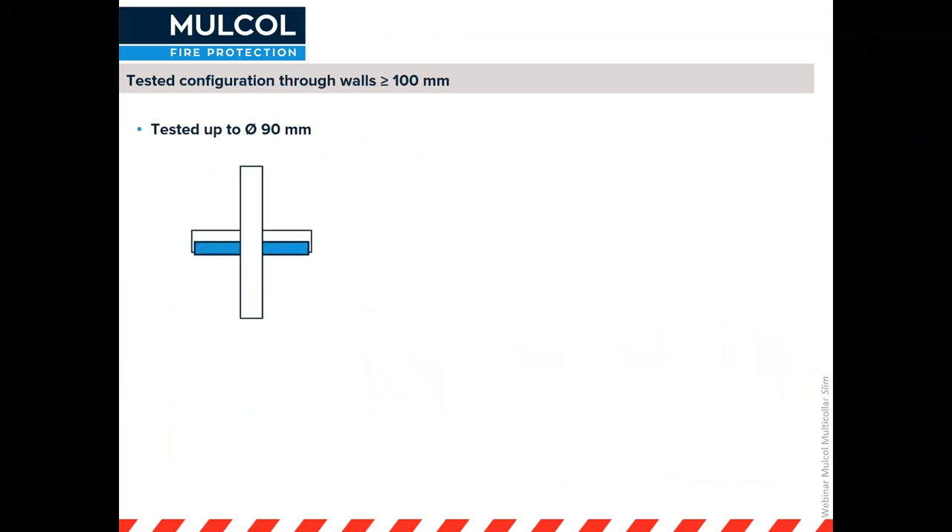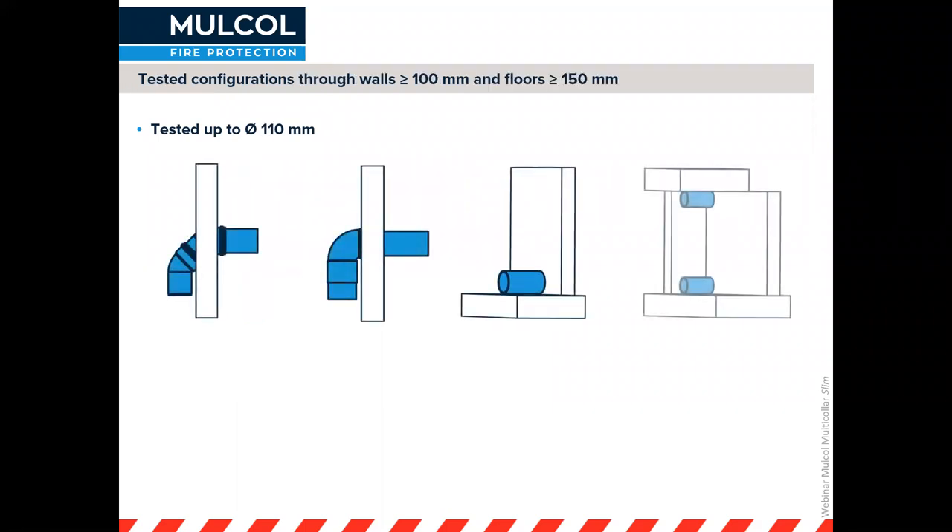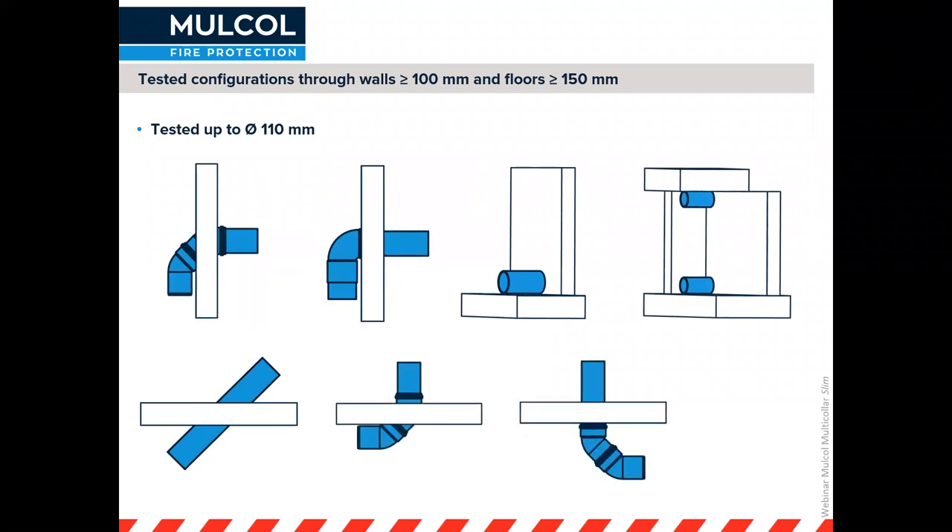The Multicollar Slim has been tested in different types of configurations. For example, where you've got a shelf or shell — a metal shell in which a plastic pipe sits — which is especially used for hot fluids where the pipe might start sagging. We've tested these configurations up to 90 millimeters, and larger pipes up to 110 millimeters.